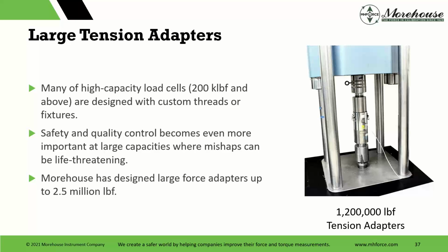Safety and quality control becomes even more important at large capacities where mishaps can be life-threatening. Yeah, if I pull something apart in a dead weight machine at 100,000 pounds in tension, it makes a loud bang. You might need to re-level the machine. Everybody's going to hear it. Things can bend. It's a pain in the butt, but generally, injuries do not occur. If you pull something apart at 5 meganewtons in tension, stuff's going places. That's a lot of force and a lot of energy, and it's not something to be toyed with.